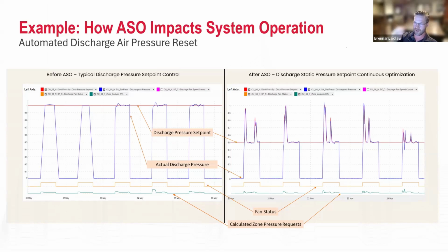So the graph on the left was the before, using a standard sequence, which is just your single set point. The red line is your set point, and you can see the blue, the pressure that goes up and down at occupancy to maintain that one static pressure set point. And the one on the right is after it's been automated.